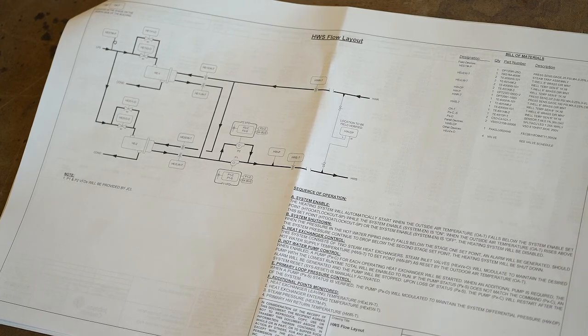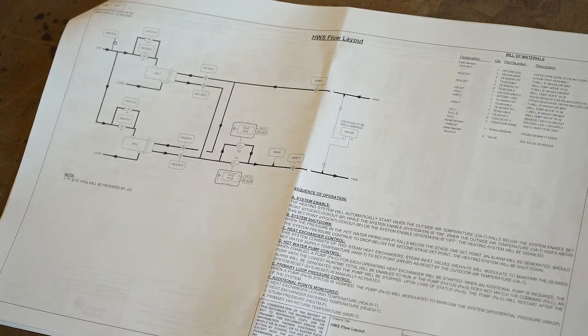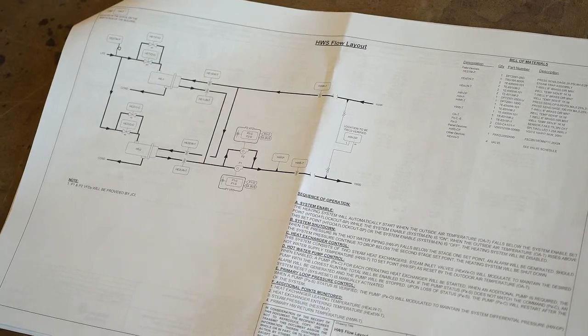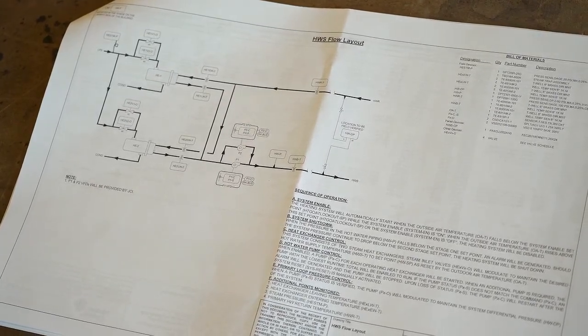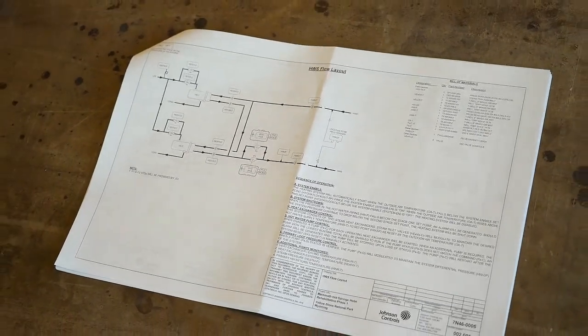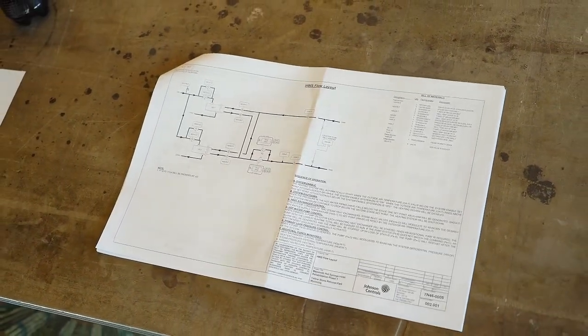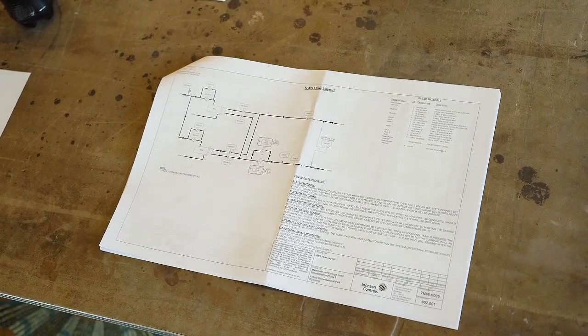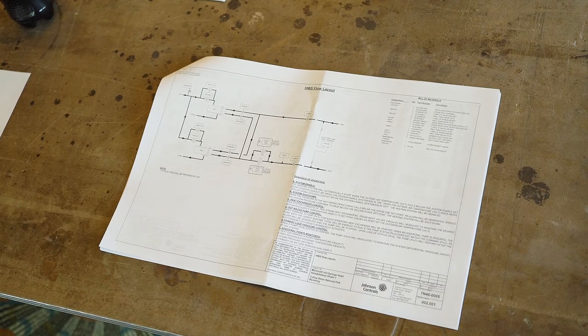I mean, you've got fin tube that's probably taking maybe 1 gallon a minute. You've got that radiant floor in the lobby. Trying to remember what else we had. You know, and the steam heat exchangers for heating the water up. And that's pretty much the load on this building. And those pumps were both going at 93% when they actually came up. And it was because of the hotel over there. So we figured everything must have been open, and none of that's on digital, so we can't tell what it's doing at this time. Well, I know we had people opening up their thermostats on their radiators because they were cold, and then they were complaining that they were too hot because, you know, they're cast iron radiators and they take forever to cool off. Right, yeah, exactly.